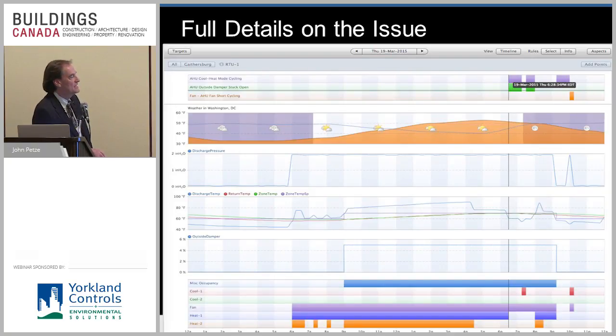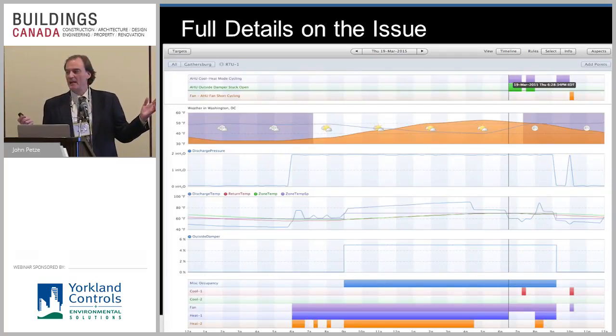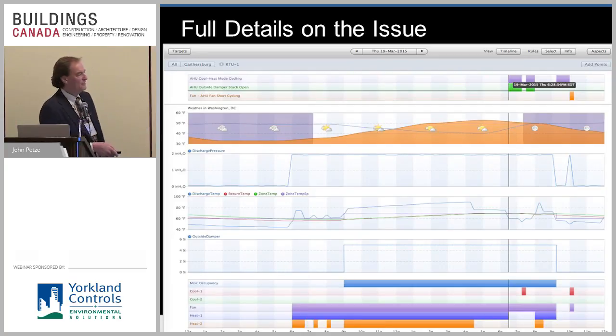And if I look a little closer, I see this, and that red little block shows me that cooling stage 1 turned on for a short period of time, happens to be about 15 minutes. Here I am in the middle of the heating day and the cooling turned on for 15 minutes. What's with that? And what did it follow it by shortly thereafter?